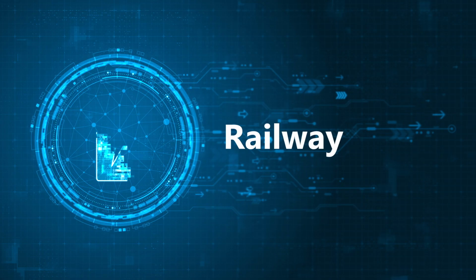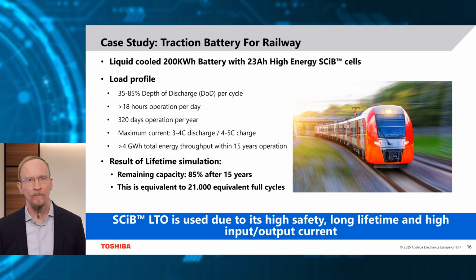One of the prime use cases for SCiB LTO batteries is the usage in traction batteries for railway due to its high safety, long lifetime, and high input-output currents. In this case study, a 200 kWh liquid-cooled battery with 23 Ah SCiB LTO cells has been used. In a typical use case, 35% of the capacity is used, but in some rare cases, the depth of discharge can be as high as 85%.